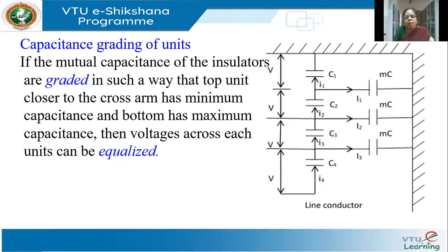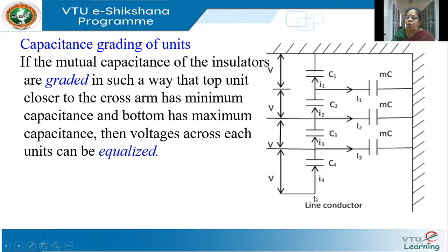The other method is grading of the insulator units, called capacitor grading. That means we don't use identical discs. We ensure that if all the mutual capacitances are equal, then we have unequal voltage distribution. So if we want equal voltage distribution — voltage V across all of them — then we must determine how the capacitances should be designed. That is the question in grading.